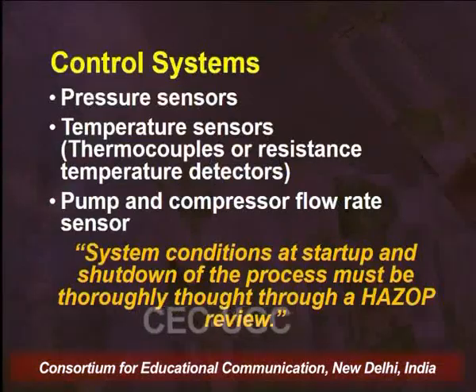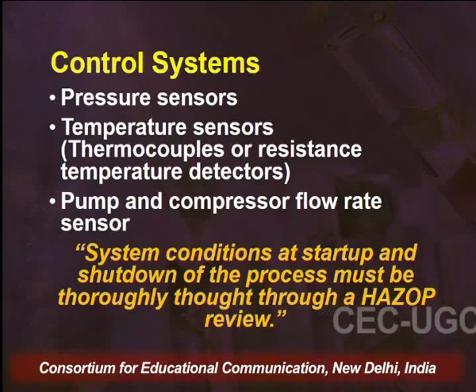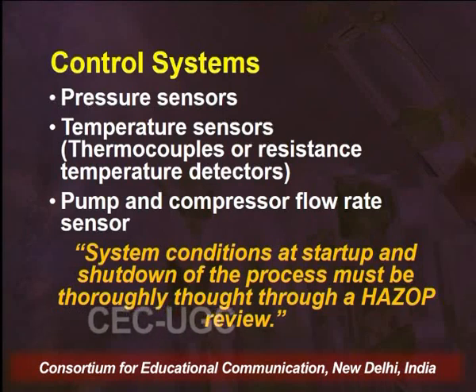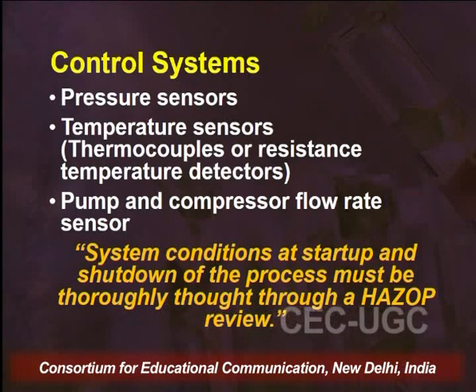Now we move on to the last component of the supercritical fluid unit, that is the control system. And control systems, as I have already told you, are the systems which help in proper functioning of the system. These include pressure sensors, temperature sensors, pump and compressor flow rate sensors. So any kind of irregularity in the pressure, temperature, flow rate is detected by these sensors, and all the inputs are sent to the control system. And the control system, as per the design, can shut down the system, they can stop the extraction unit if any kind of irregularity is found in these parameters.